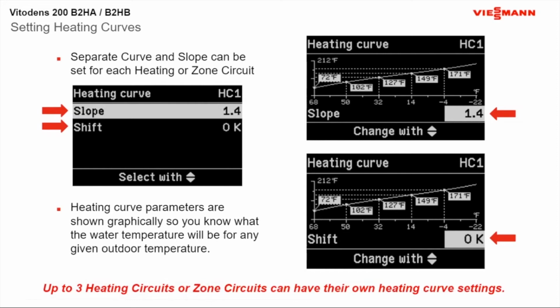So in a lot of cases, like I always use my mom as an example at 87, her thermostat set at 87. If we went into warm weather shutdown at that temperature, I would definitely get a phone call saying that she's too cold. So you can raise and lower the bottom end of the scale as well. So your warm weather shutdown is higher, as well as you're going to have hotter temperatures down at the lower end of the scale. So you're kind of flattening out your curve, basically.